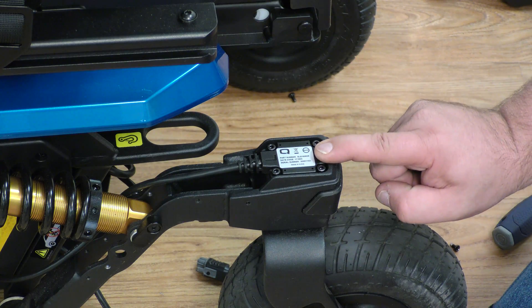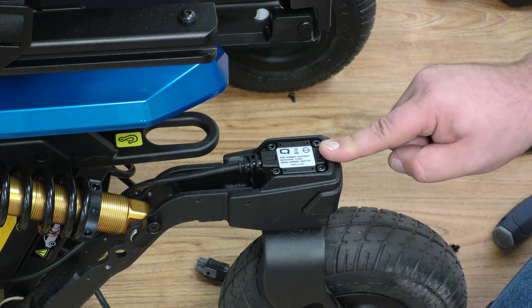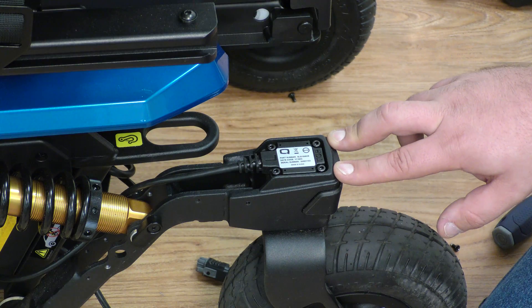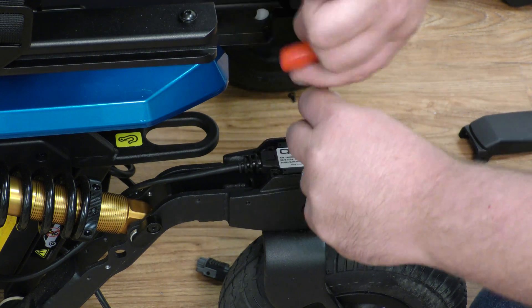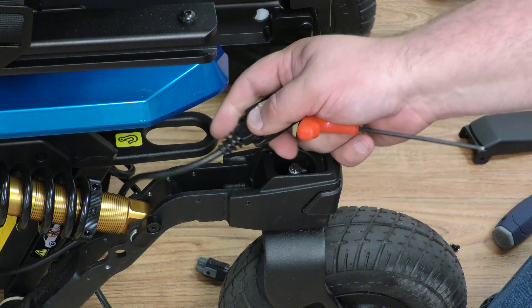This right here will be your caster sensor. The caster sensor maintains the stability of the forefront. To remove the caster sensor, there are four three-millimeter Allen head screws that hold the sensor in place. Remove each screw, then remove the caster sensor.